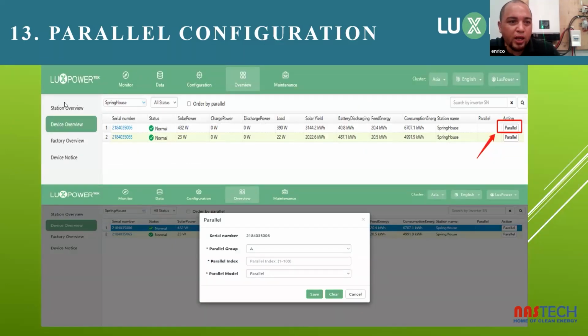When doing the config online on the web page, some of the installers are not always aware that they need to set the inverters in parallel. You need to go online to set the inverter in parallel. You can have 2 inverters wired up in parallel, all the dip switches correct, but they're not working together in parallel. They're giving out standalone power, and sometimes they're performing very differently to what you've expected from these 2 being in parallel.